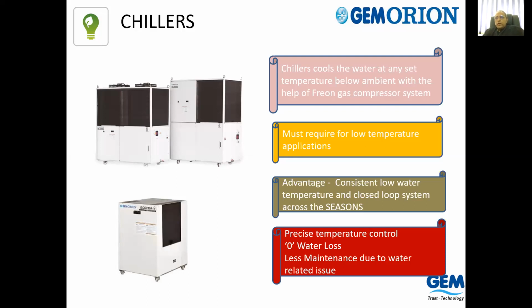The greatest advantage of this system is you don't need two cooling water systems coming from the utility part to the factory side. For example, if you have multiple machines, then having a separate chiller for mold and a separate cooling tower for the hydraulic process, you are forced to use two separate piping lines. You have a heat exchanger, cooling tower, evaporation, water loss, tank, and it becomes very complicated in the factory to run and maintain these water lines. Two kinds of water lines, one with scaling, one without scaling. Because normally in a chiller you have a closed loop, so you don't have any scaling happening. It's only a complete heating and cooling. Maybe once in a year or so you just make up or change water.